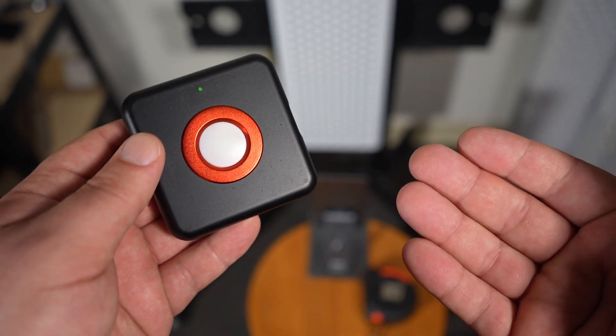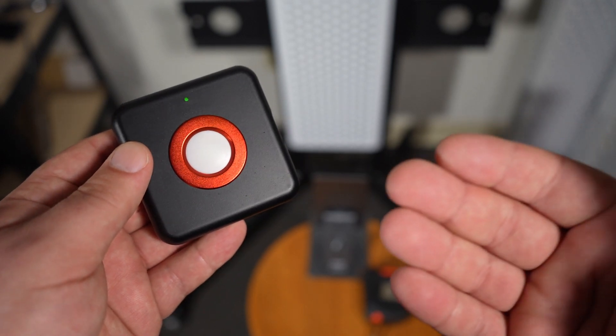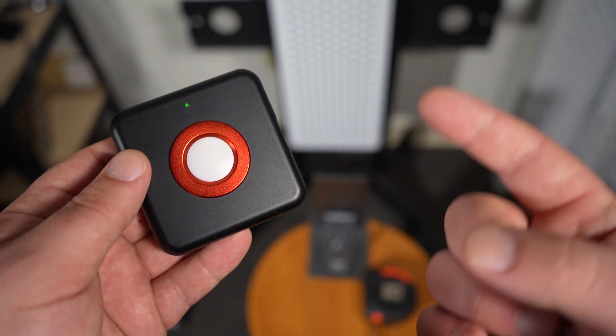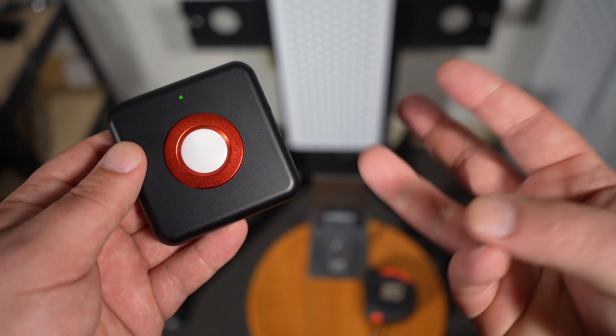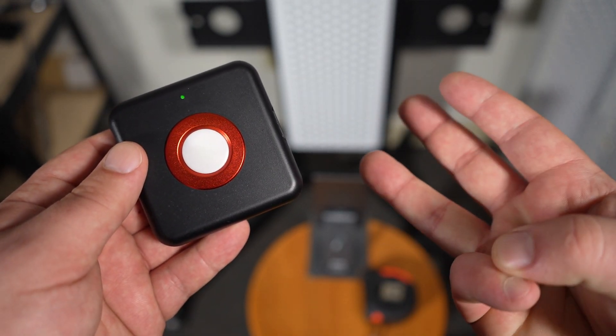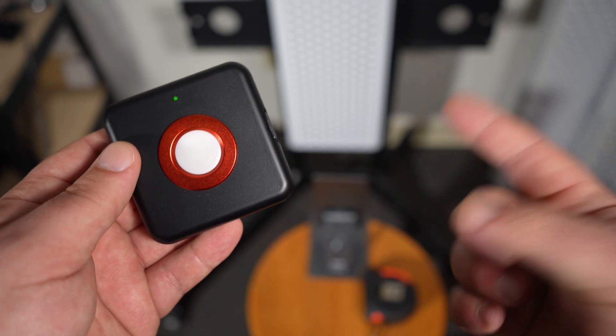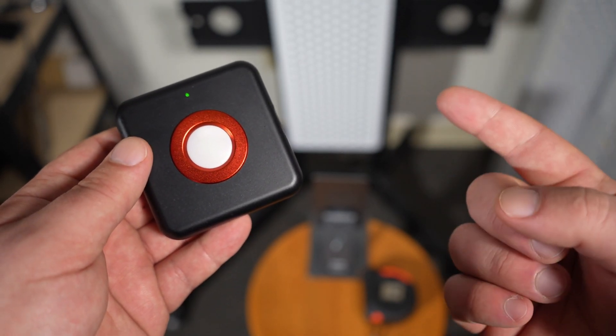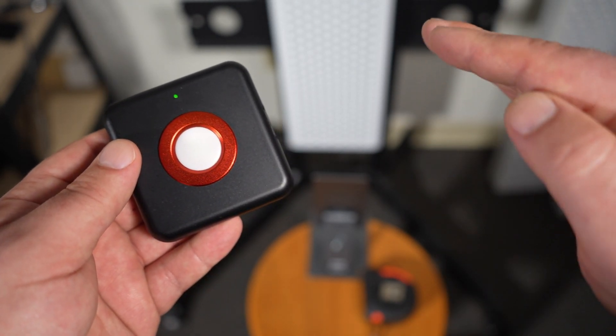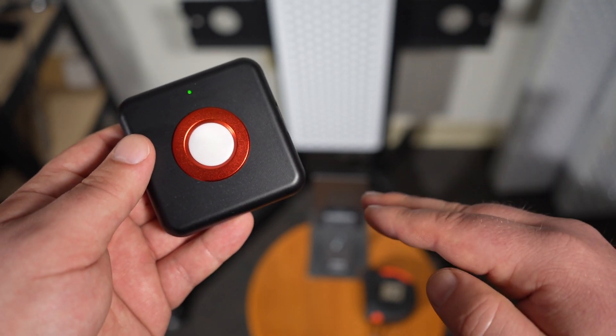I'll give you the quick verdict: it is good at measuring 630, 660, and 850 nanometers. It's not so good at measuring 810. It seems to measure it falsely low.